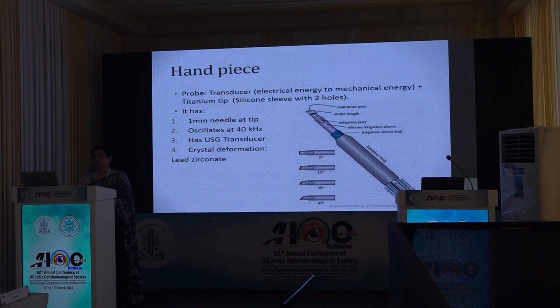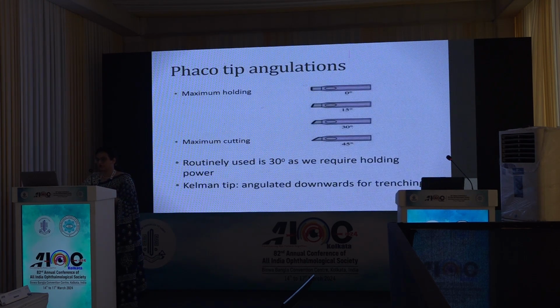We have a phaco probe which has a transducer that converts electrical energy to mechanical energy, and it has a titanium tip, and a silicone sleeve covers the titanium tip. It has a 1 mm needle at the tip and oscillates at 40 kilohertz. It has a USG transducer, and lead zirconate crystals are present, where deformation of the crystal leads to the generation of energy.